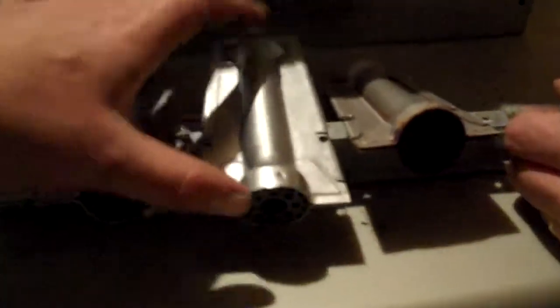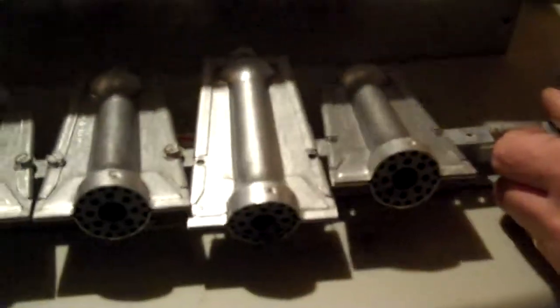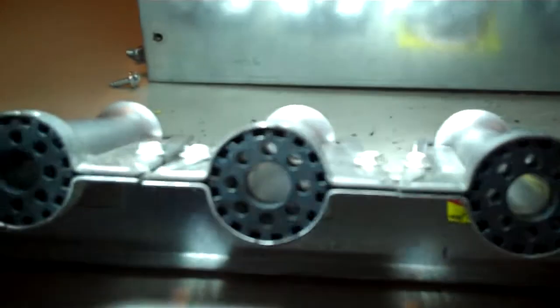Alright, he's doing one, I'm doing that one. Pretty simple. And now you'll see we have a nice string of burners all lined up nice and clean. And if you look way down in there, see that on the sides there? See a little gap? That's where your gas is going to want to come out. See that one's blocked off on the side a little bit? And that one's wide open.